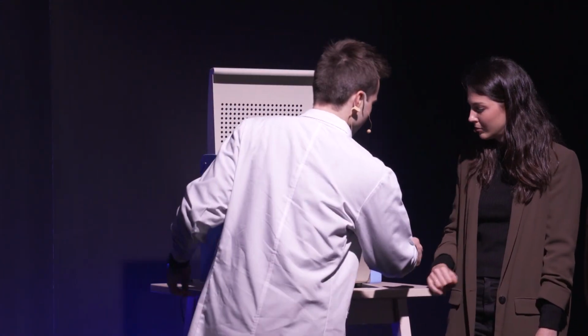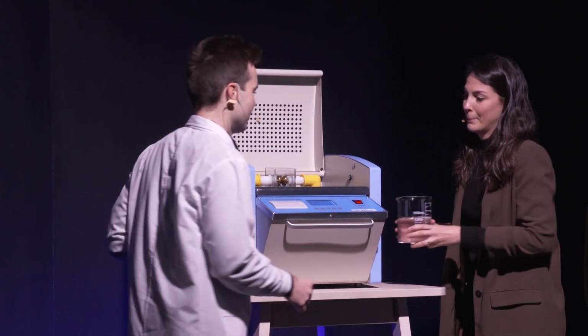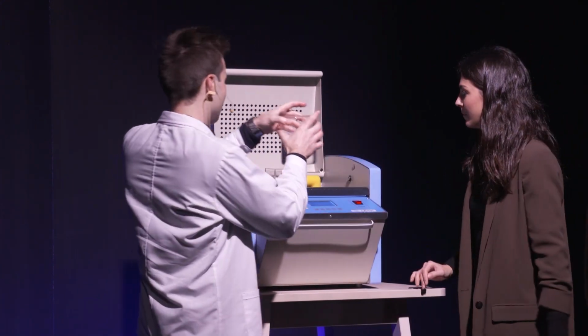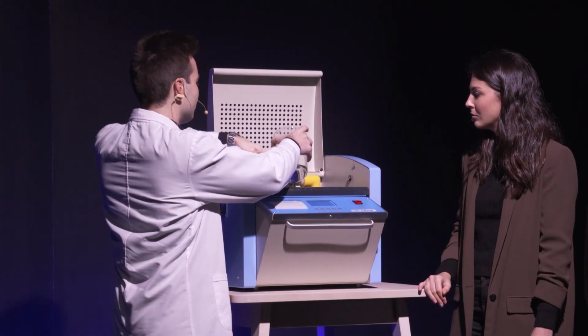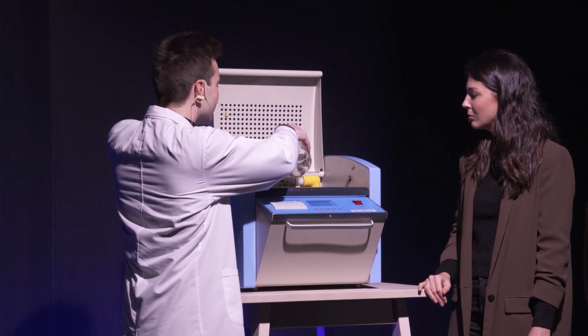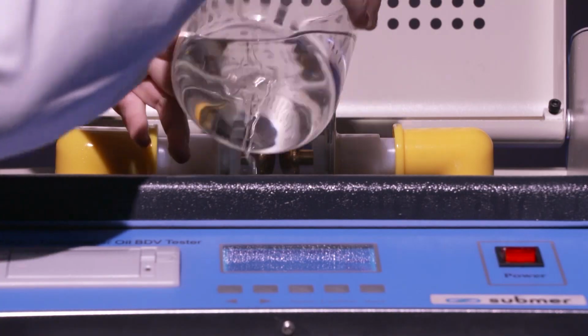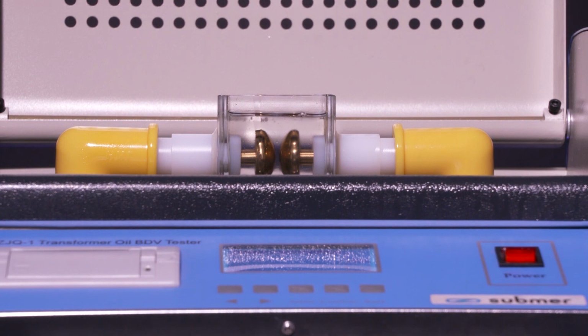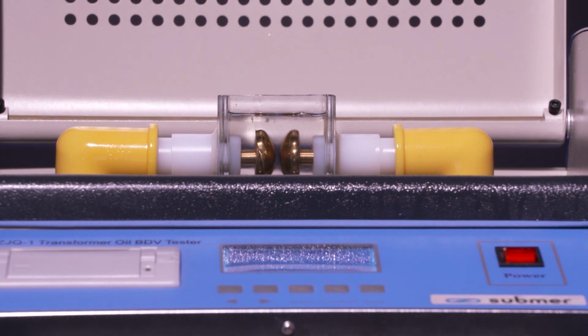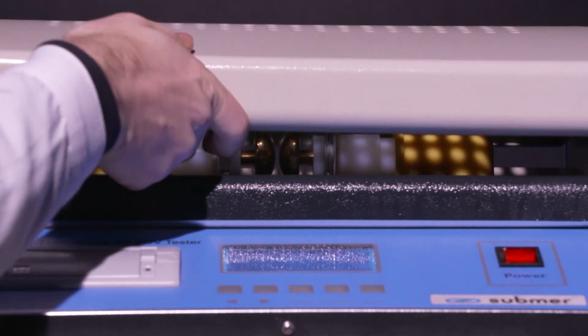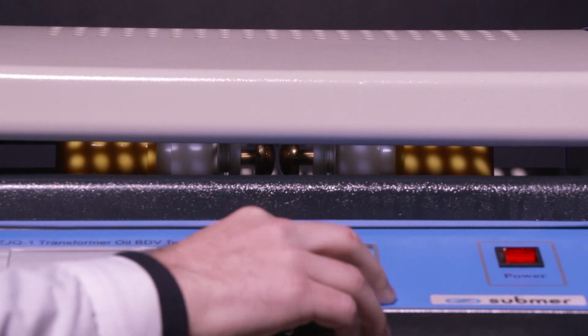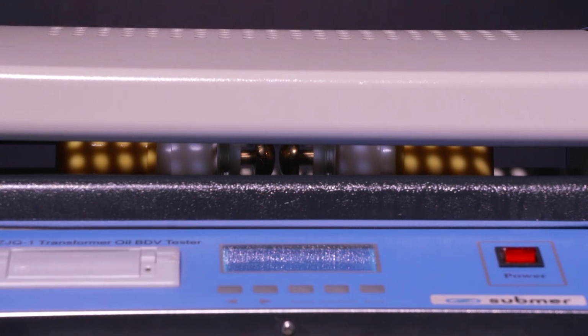Now let's take the Smart Coolant and repeat this test. You would expect that being a liquid, it would take a far shorter time for there to be a spark, but let's see if that's true. Start the test again - now we're ramping up that voltage. We're now over 10,000 volts, and there's still been no spark.